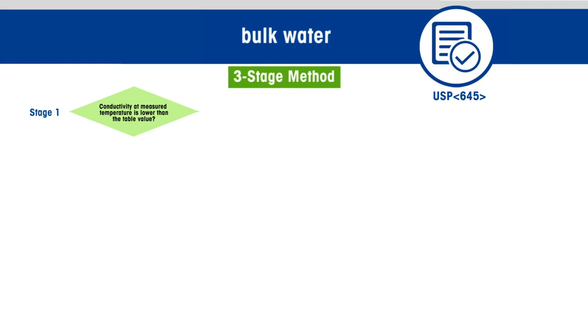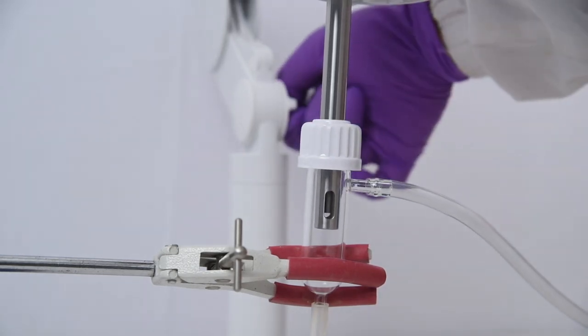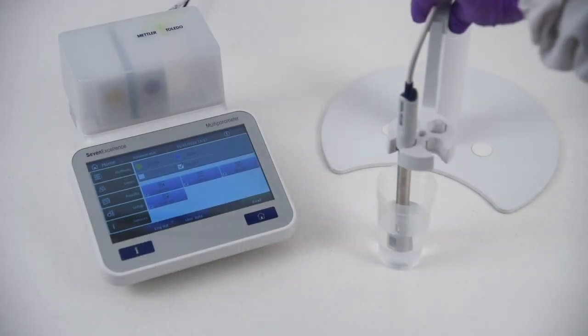For stage one, conductivity and temperature are measured. If the conductivity at the measured temperature is lower than the table value, the water meets the requirements. This stage can be performed using a flow-through cell for an online measurement or performed in a suitable container without stirring.